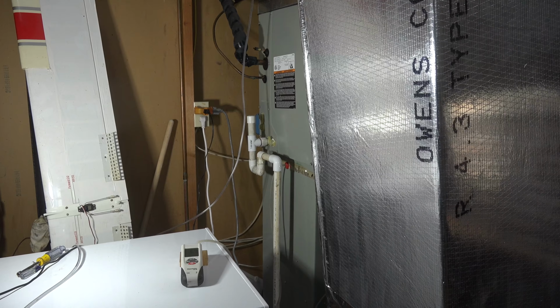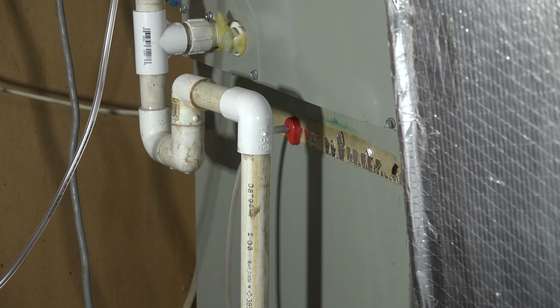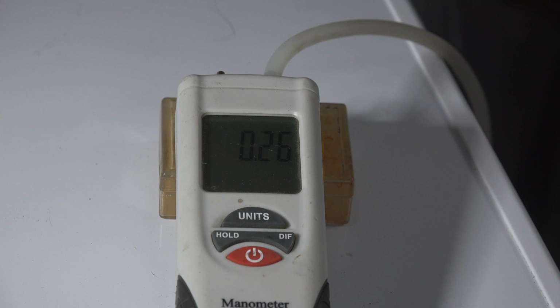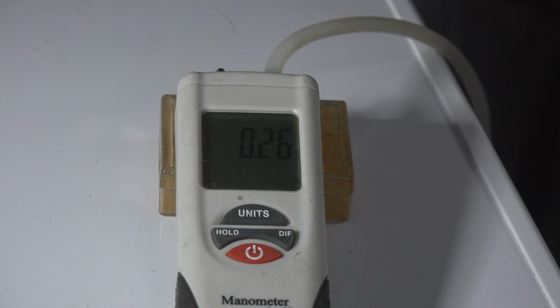So let me show you where I've got this probe. Now you should have seen this probe last time I did total static pressure. It's right at the outlet of the furnace, and with only that one hooked up, we should be reading the total static pressure of the supply system. That's the total resistance to flow of the entire supply system. Let's look at what that is.